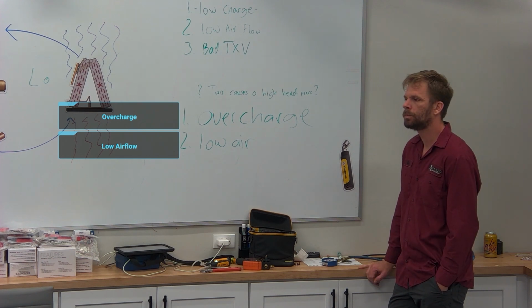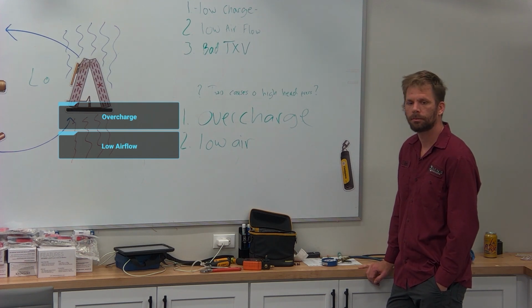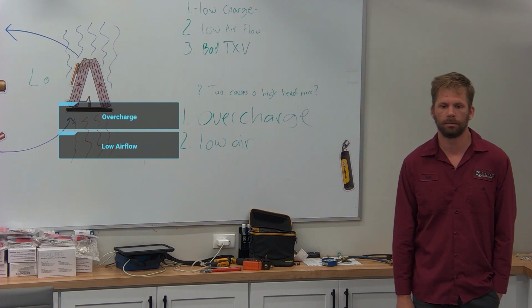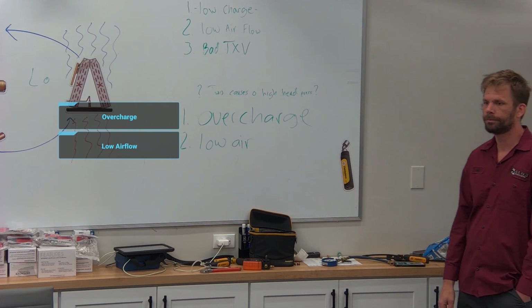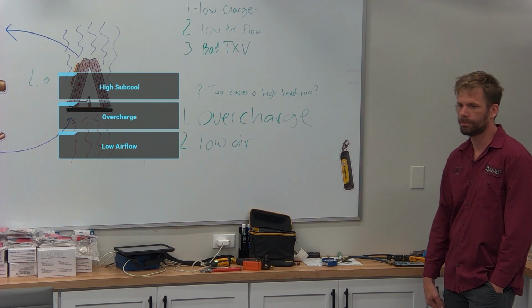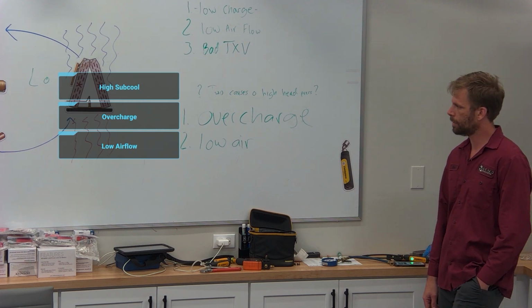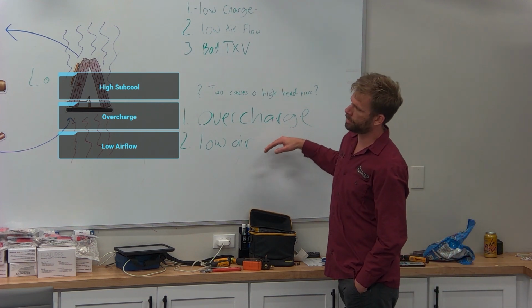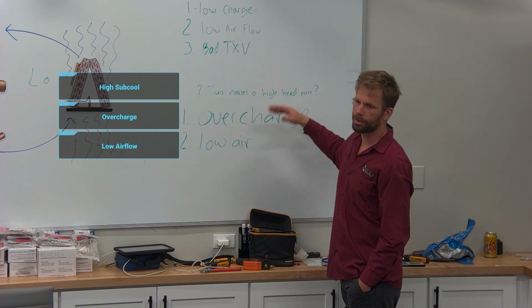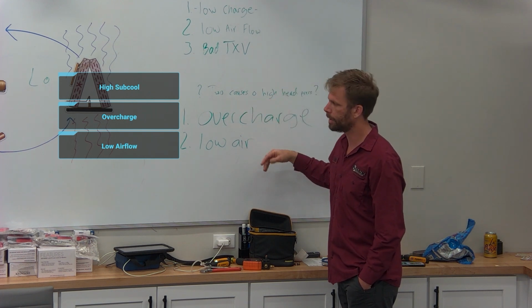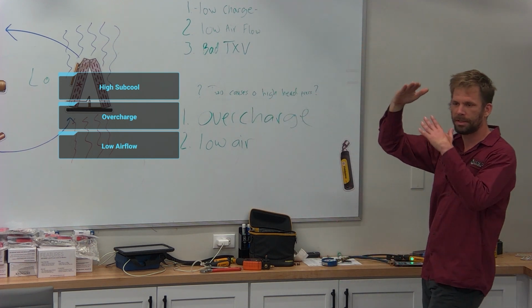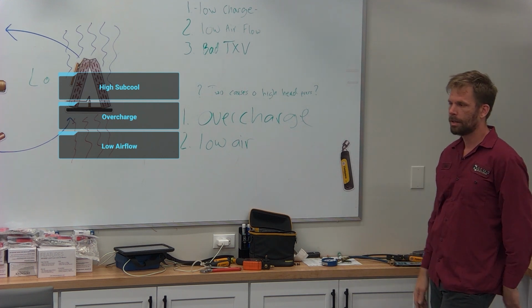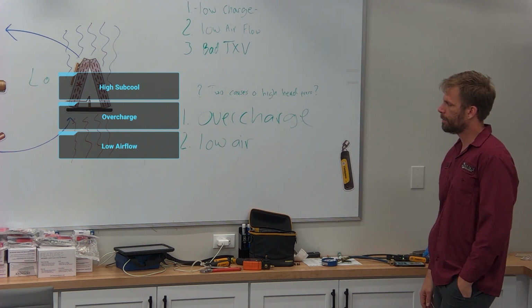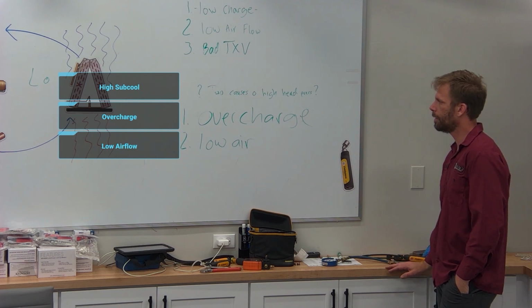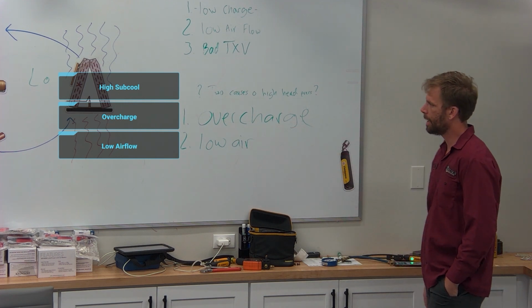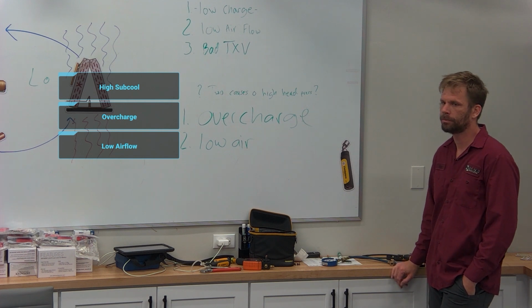I mean, the overcharge. I was gonna say maybe for the overcharge, I mean, we know we look at subcool for refrigerants. Yeah, overcharge, really high subcool. If it's just low air, your subcool stays close to the same, just all your temperatures go up. Higher liquid line temperature, higher saturation, but they still stay pretty close to the same. If anything, once it gets bad, it gets lower subcool. But overcharge, you're gonna have very high subcool.